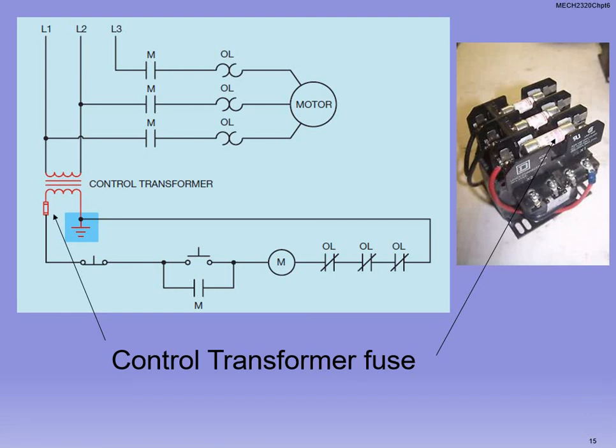All right, so hopefully all this is starting to come together here, and we can see where and how the control transformer is used. Main power coming in, and then we step it down. Because remember, we don't use high voltage for controls. We use low voltage for controls. We use high voltage to run our motors and machinery and equipment that need it, so that they can work through and handle higher loads.